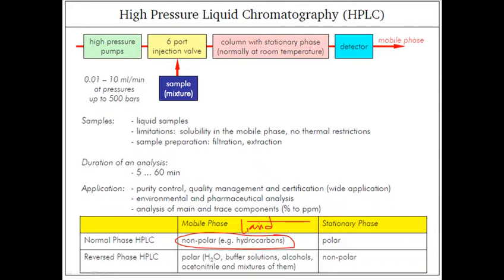In this case, we have a high pressure pump through which the pressure is created. You inject the sample in the six-port injection valve, and the sample is carried out by pressure via the mobile phase molecules. It will carry through and eventually end up at the detector. The detector feeds it into a computer screen, elution is done of the mobile phase, and finally you can see a chromatogram.